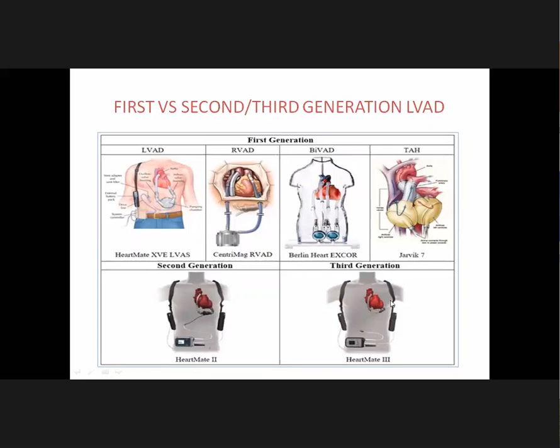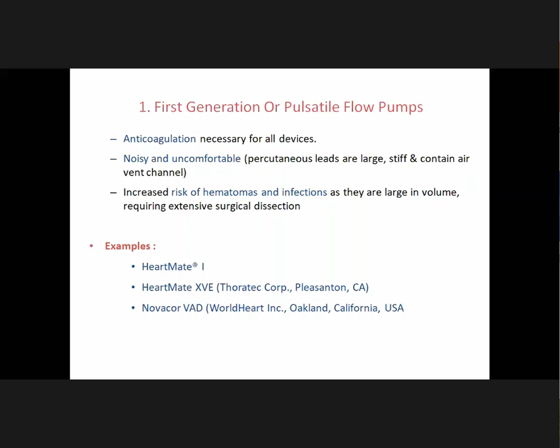I'll be discussing the basic underlying points of first generation, second generation, and third generation. The major disadvantage of first generation or pulsatile flow systems is that they require anticoagulation for all the devices. It is very noisy and uncomfortable for the patients because of percutaneous leads, which are large, stiff, and usually contain air vent channels because they are pneumatically driven. Then they have increased risk of hematomas and high chance of infections as they are large in volume and require extensive surgical dissection. The commonly used first generation or pulsatile flow pumps are HeartMate 1, HeartMate XVE, and Novacor ventricular assist device.